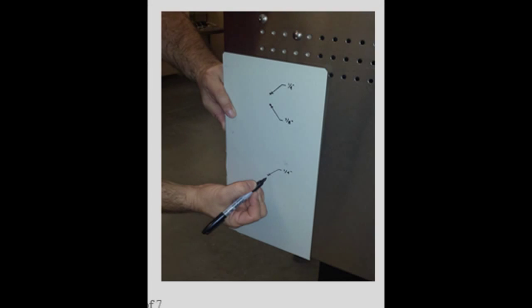Align the drill template supplied with the heater kit on the front and bottom edges of the right side of the enclosure as shown. Use the template to mark the three hole locations to be drilled. Drill each hole to the size noted on the drill template. Use a step drill bit or hole punch hole saw to drill the 7/8 inch hole.